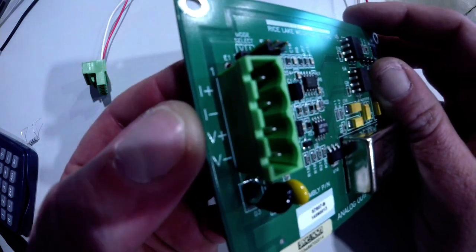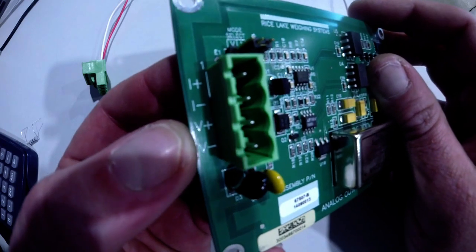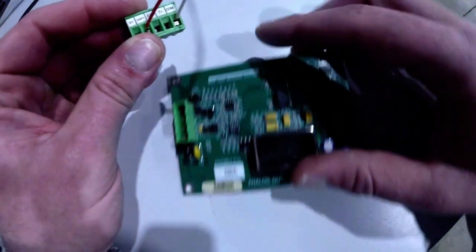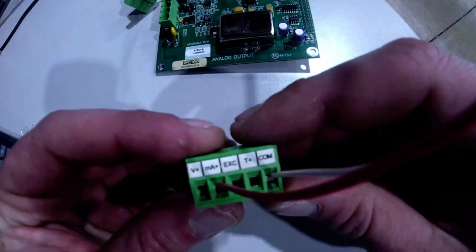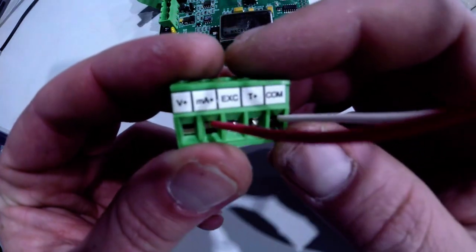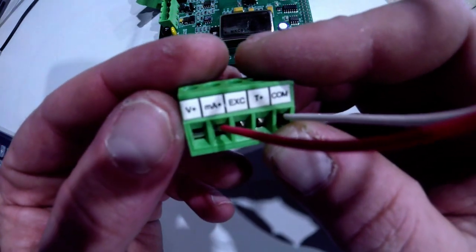On the side of this terminal it explains we have I plus and I minus, that's current plus and current minus, or voltage plus and voltage minus. On the back of our connector for our process meter, it's nicely labeled on the connector itself. We have our common, V plus if we were using a voltage output.